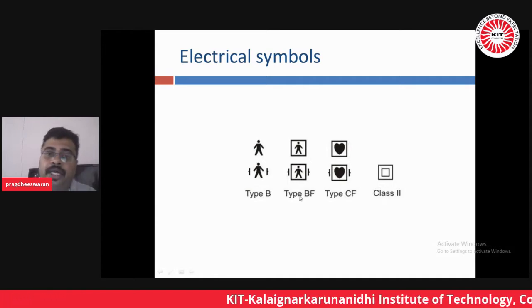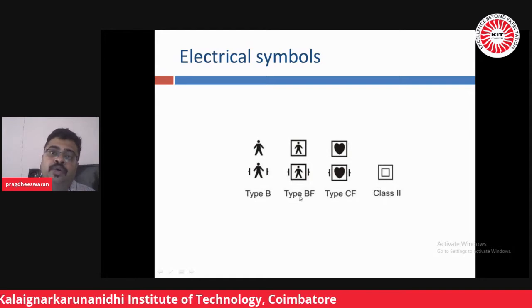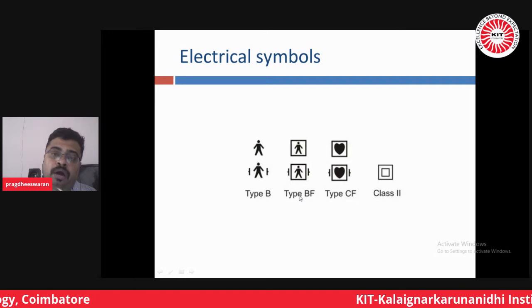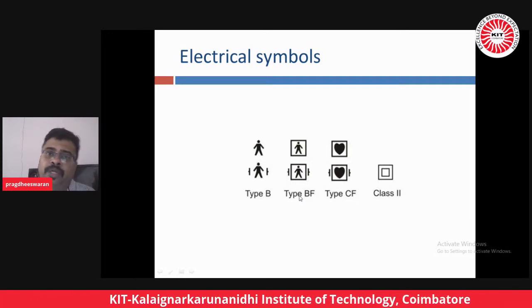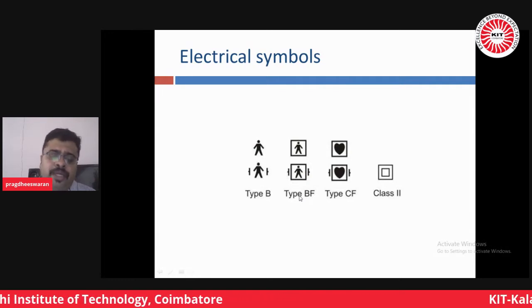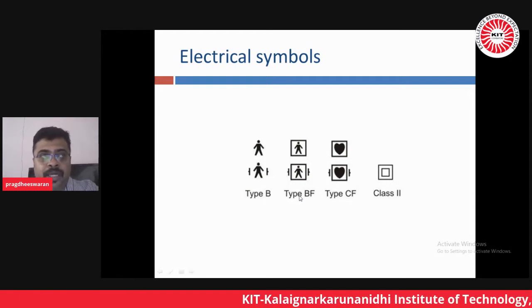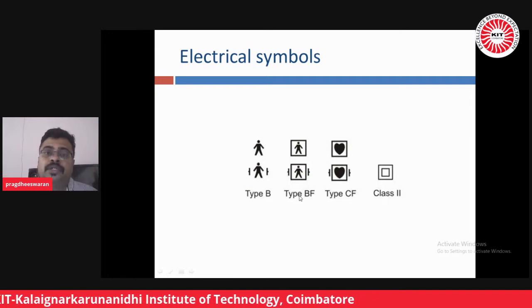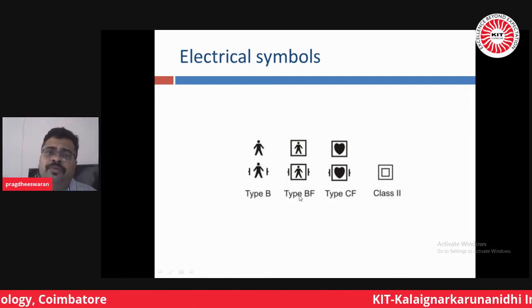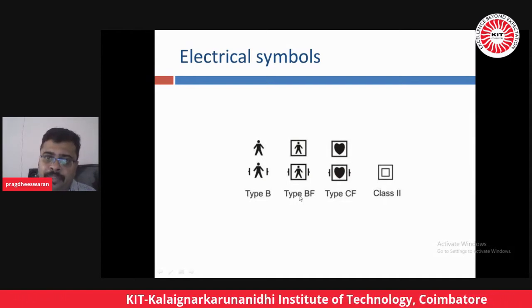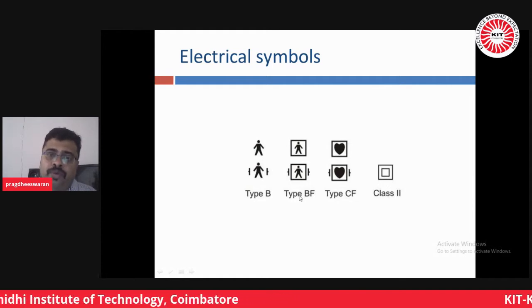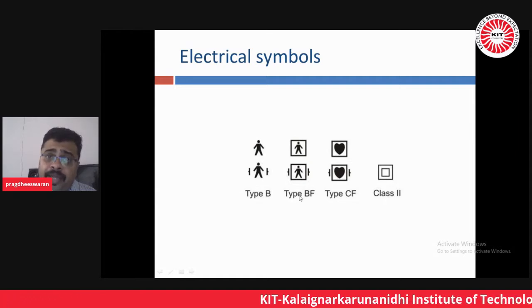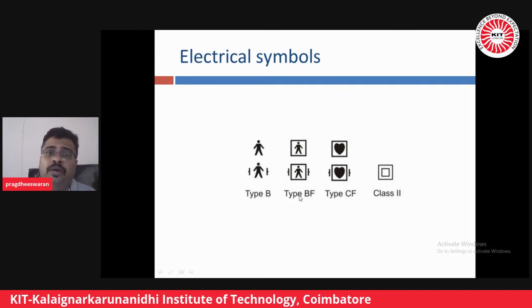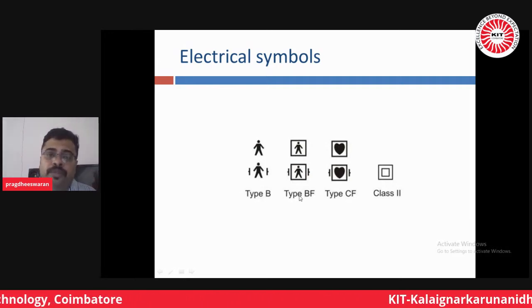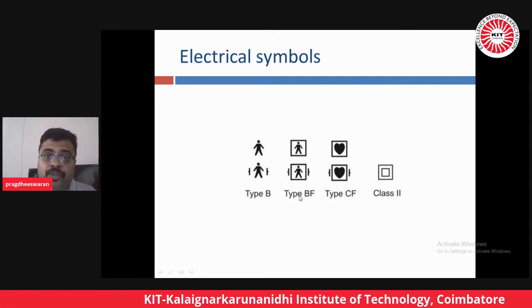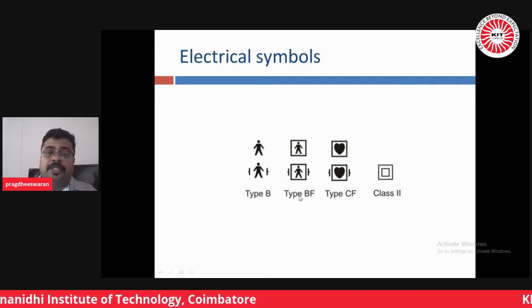So the collateral standard says that you take any equipment, X-ray, ECG equipment, a defibrillator kind of dangerous equipment, a dialysis equipment, a ventilator, whatever the equipment, or even a needle syringe destroyer, a very simple equipment in the medical industry, you have to follow certain standards to test your equipment. But collateral standards are very wide. A manufacturer needs to worry so much about collateral standards: I have to pass my equipment with the EMC test as per IEC 60601-1-2, and 60601-1-8, which says alarms are also designed as per the protocol. I cannot simply make an alarm make a sound. It should have a dB level and a flashing range; everything should be determined.